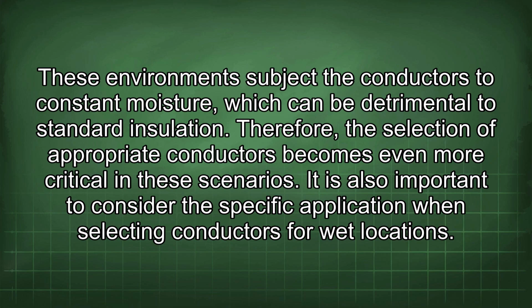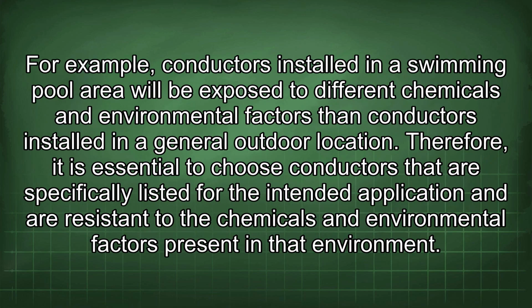It is also important to consider the specific application when selecting conductors for wet locations. For example, conductors installed in a swimming pool area will be exposed to different chemicals and environmental factors than conductors installed in a general outdoor location. Therefore, it is essential to choose conductors that are specifically listed for the intended application and are resistant to the chemicals and environmental factors present in that environment.